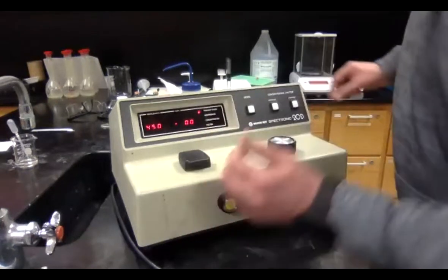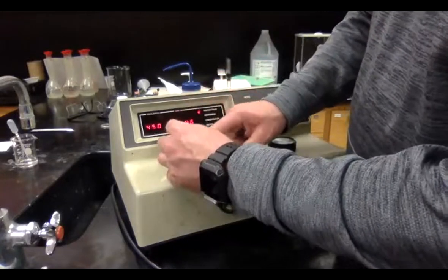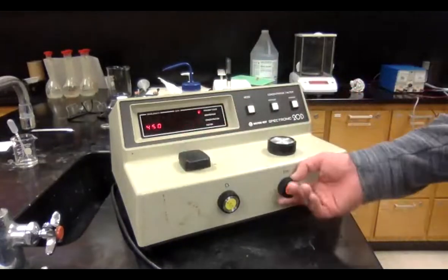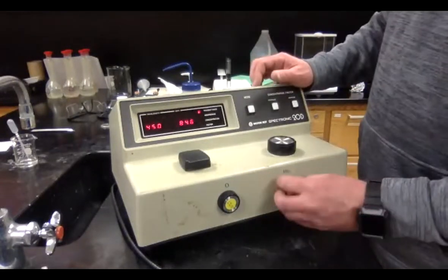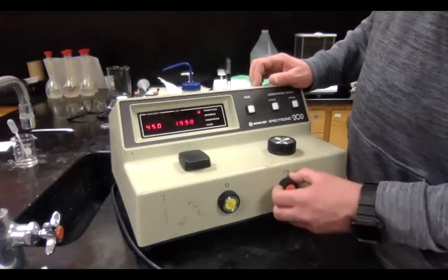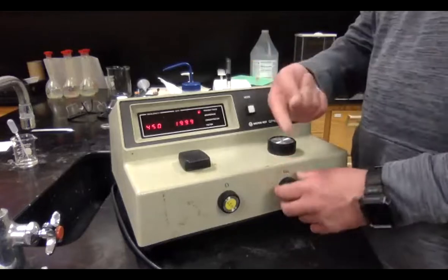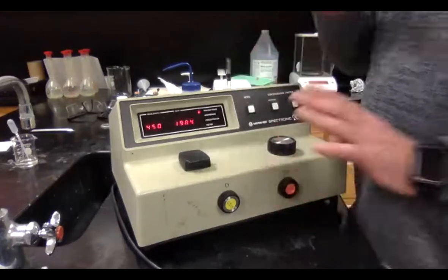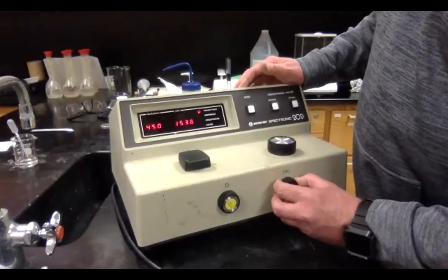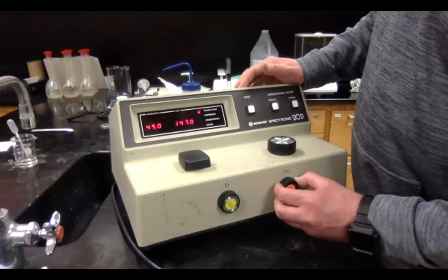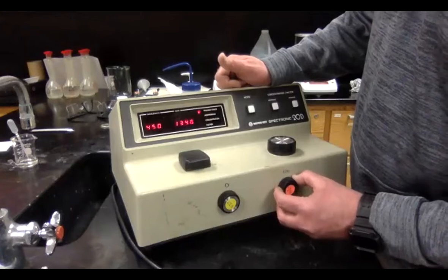How much fun is this though, right? Blanking. So we want that to be at 100. You can see some people are like, well, I'm turning it and it's not changing. That's the beauty of an analog thing. You can keep turning it. Never force these though. Never ever force these. So I'm going to get this down to transmittance of 100. So 0 without anything in there, 100 with just distilled water.